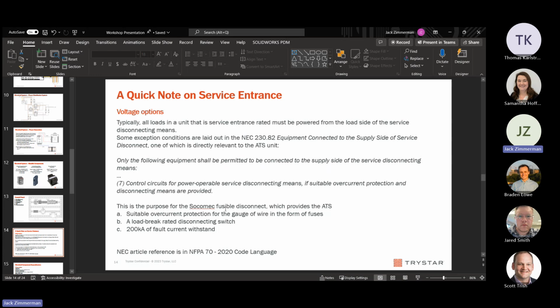So the article reads, only the following equipment shall be permitted to be connected to the supply side of the service disconnecting means. And there's 11 examples, but the 7th is control circuits for power operable service disconnecting means, if suitable overcurrent protection and disconnecting means are provided. So this is directly related to what we're talking about. We are making a power operable service disconnecting means. And in our case, the Socomec fusible disconnect I talked about has suitable overcurrent protection for the gauge of wire we use going through it. It is load break rated, which is really important. And these three things are, if we ever need to switch it, the standards we have to meet.